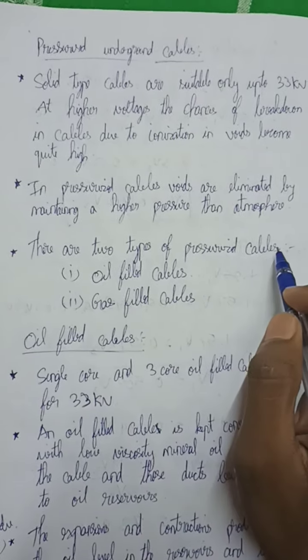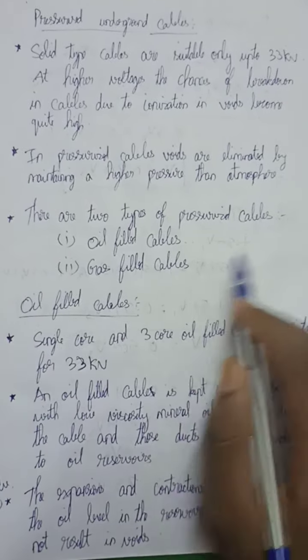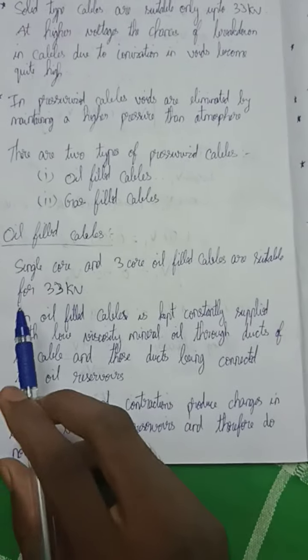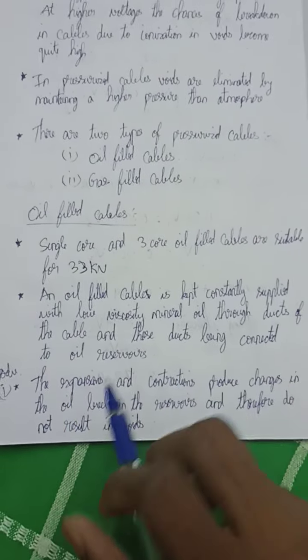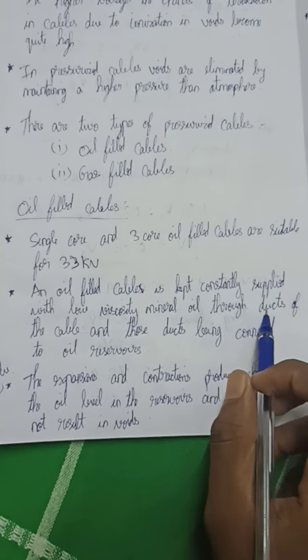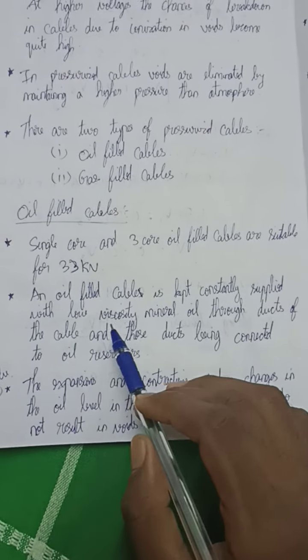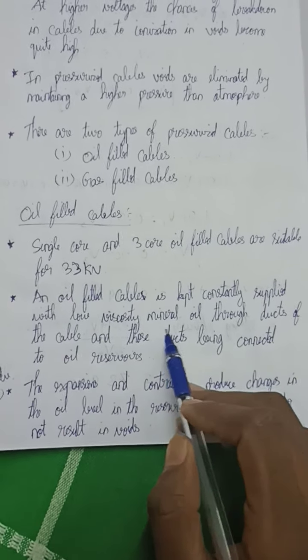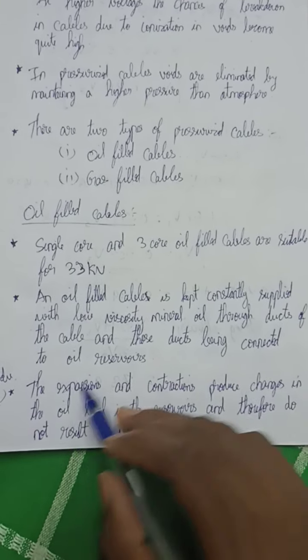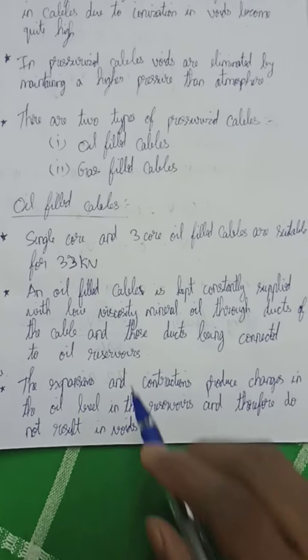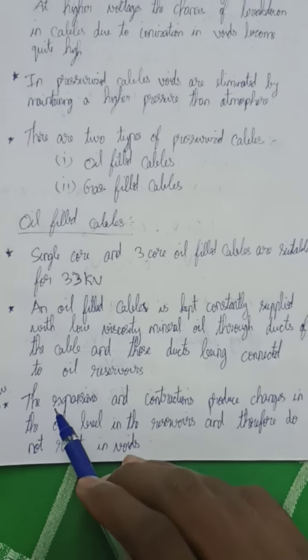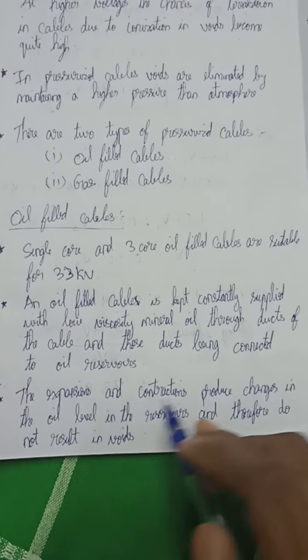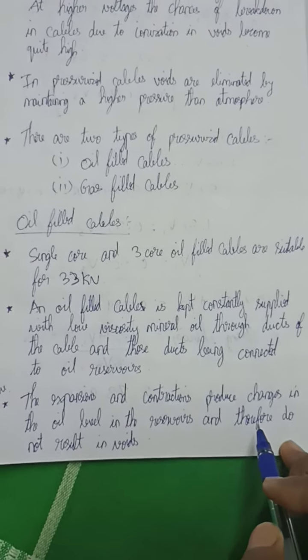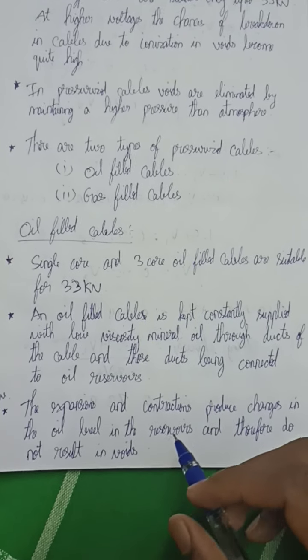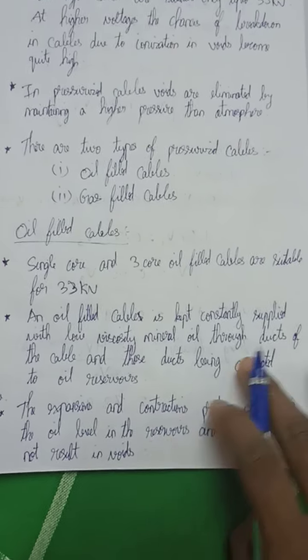There are two types of pressurized cables: oil filled cables and gas filled cables. Single core and three core oil filled cables are suitable for 33 kV. An oil filled cable is kept constantly supplied with low viscosity mineral oil through ducts of the cable, and these ducts are connected to oil reservoirs. The advantage of oil filled cables: the expansion and contraction produce changes in the oil level in the reservoirs and therefore do not result in voids. That is the main advantage.